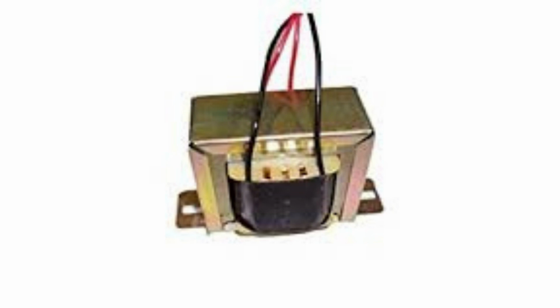Isolation: the transformer can be used to isolate different parts of an electrical system from each other. This can be useful in situations where it is necessary to protect sensitive equipment from electrical noise or power fluctuations. Grounding: the transformer can be used to provide a neutral point for grounding purposes. This is useful in situations where the utility power source does not have a neutral point, or where the neutral point needs to be moved to a different location.